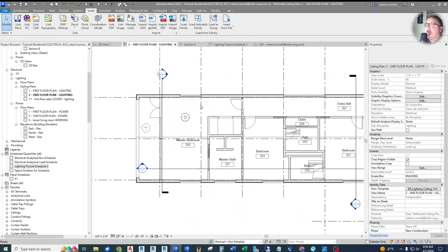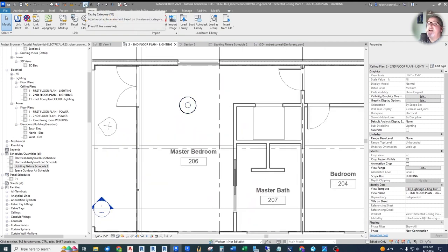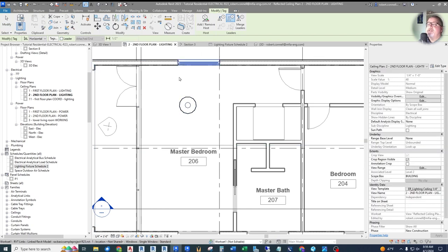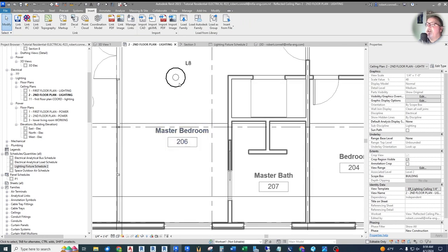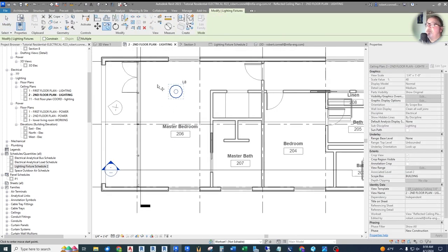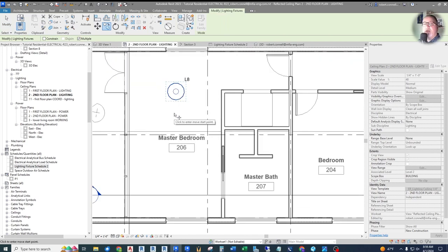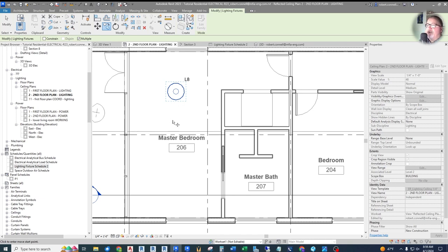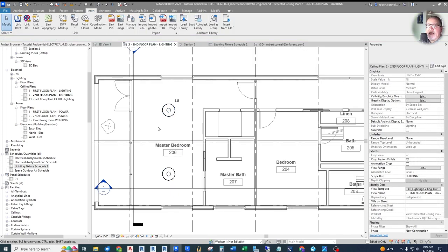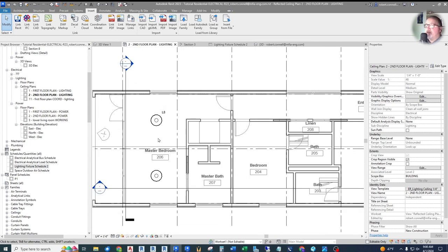We can tag this fixture — we already created a tag that reads the fixture type, so turn off the leader and click to tag it as L8. Being unhosted, this fixture can be freely copied around the plan. There's quite an argument that unhosted families should be used all the time, especially for lights — you'll encounter models early in design that have no ceilings at all, so there's nowhere to place a hosted fixture. Unhosted lights make your life much easier.